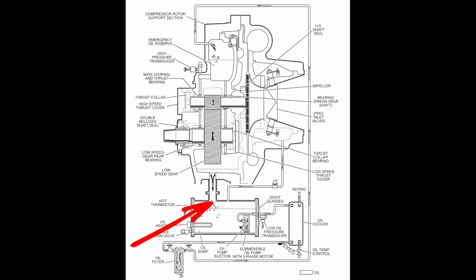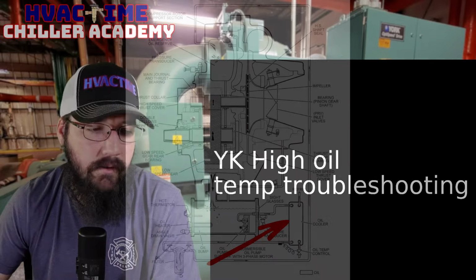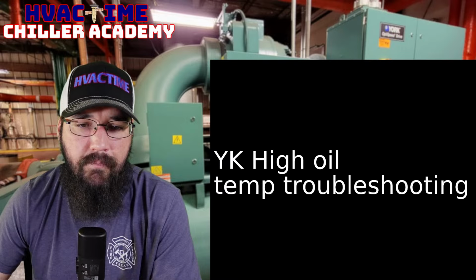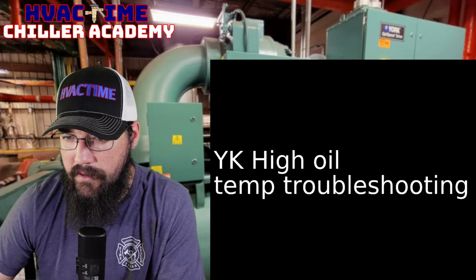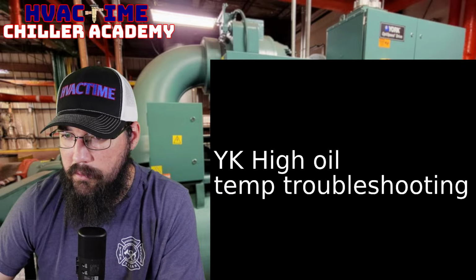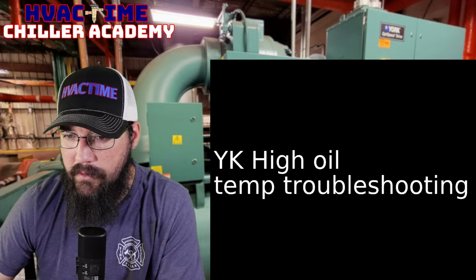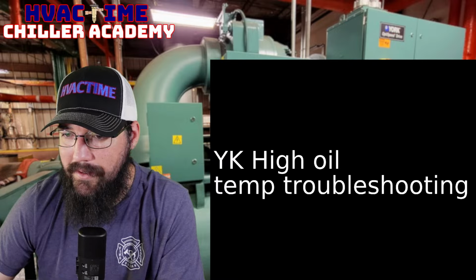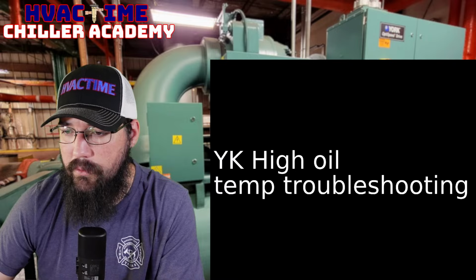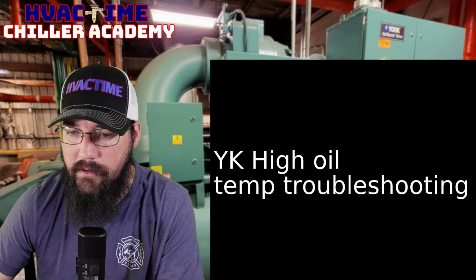Every troubleshoot like that I've had, it was somewhere in here. It was either a sensor, it was something weird with the heater, or the oil cooler itself was just not functioning correctly for the variety of reasons I described. Let's see. So you had some other commentary. Running normal conditions, set point. A little more info: condensing water temps got high due to tower fans not controlling properly. Okay.